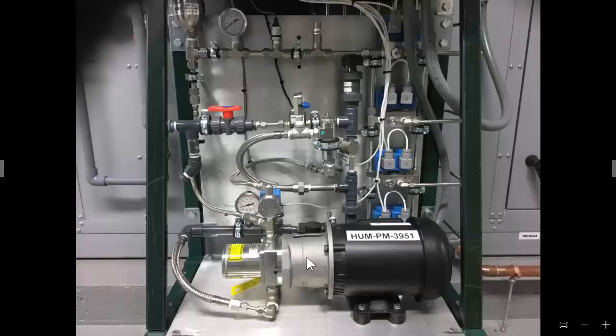One of the other items in the output piping is a check valve right here. This is a check valve to make sure that water only goes in one direction, and when the system shuts off, it makes sure that high pressure water from the discharge side does not make its way back into the input side of the pump. There is also a solenoid valve here, and this solenoid valve is part of the bypass line, and we'll cover that in a separate video, but I just wanted to point that out at this time.